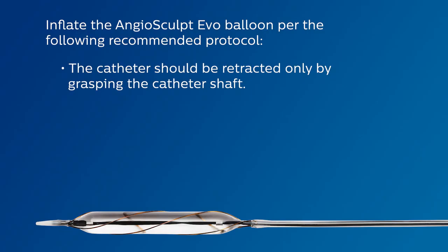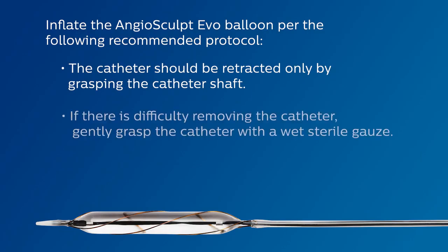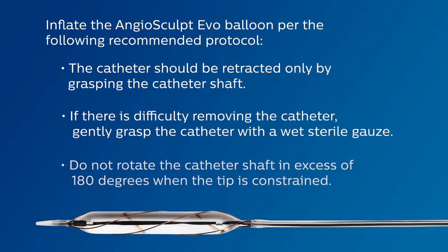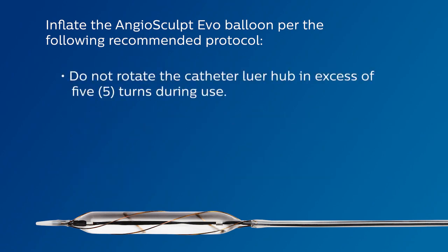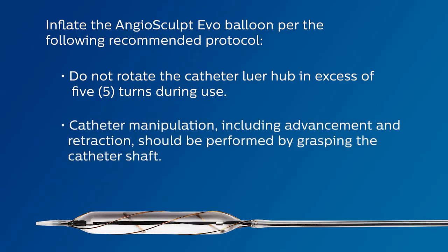The catheter should be retracted only by grasping the catheter shaft. If there's difficulty removing the catheter, gently grasp the catheter with a wet, sterile gauze. Do not rotate the catheter shaft in excess of 180 degrees when the tip is constrained. Do not rotate the catheter luer hub in excess of 5 turns during use. Catheter manipulation, including advancement and retraction, should be performed by grasping the catheter shaft.